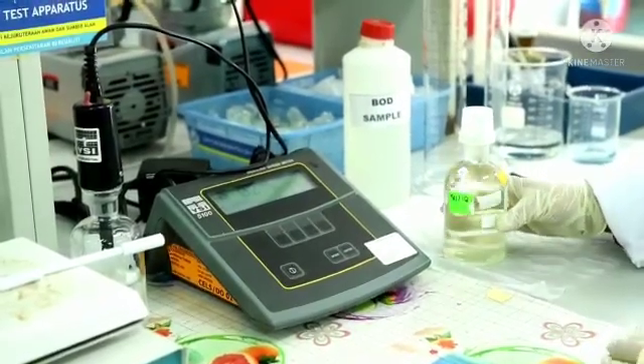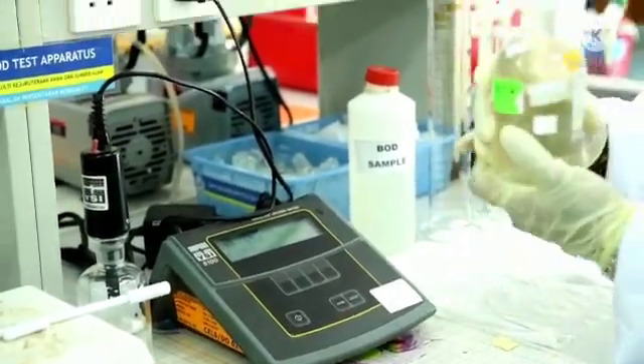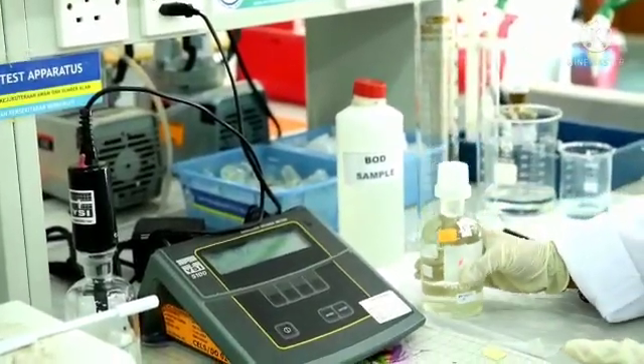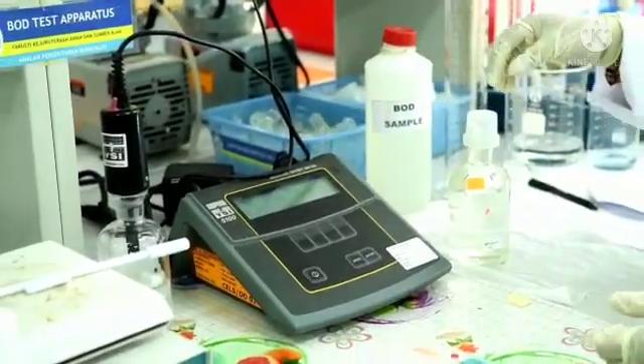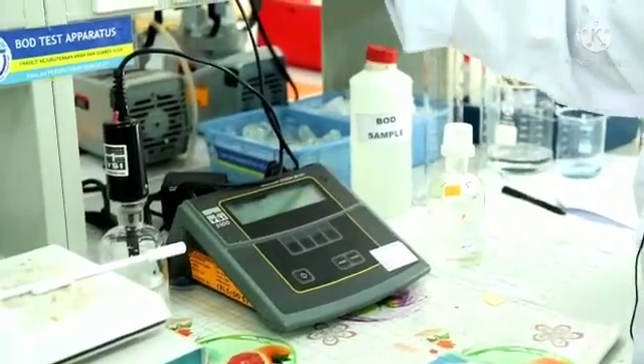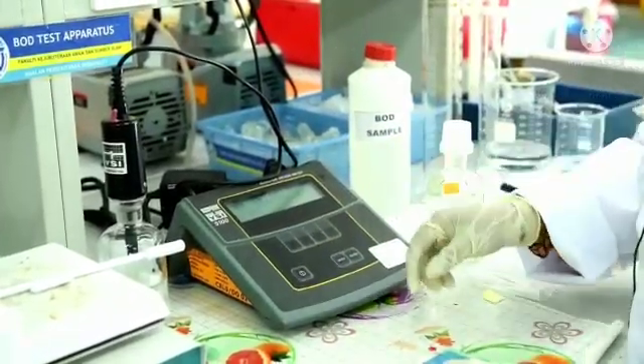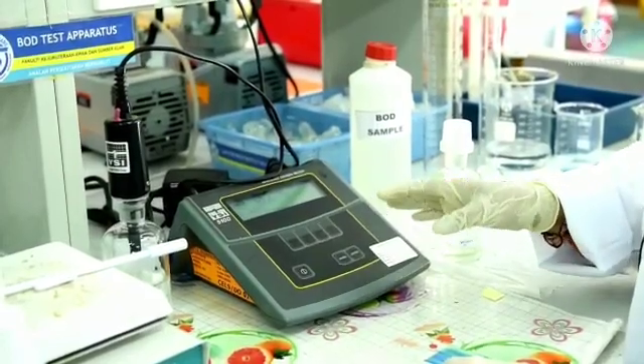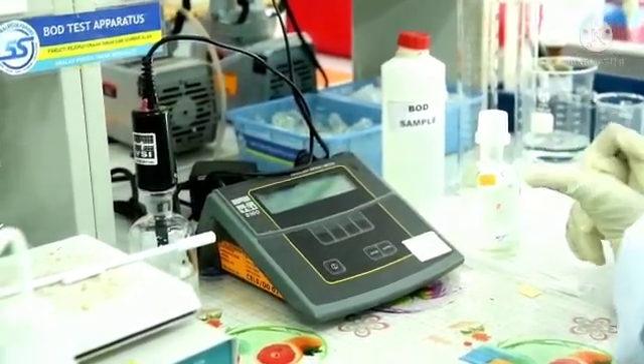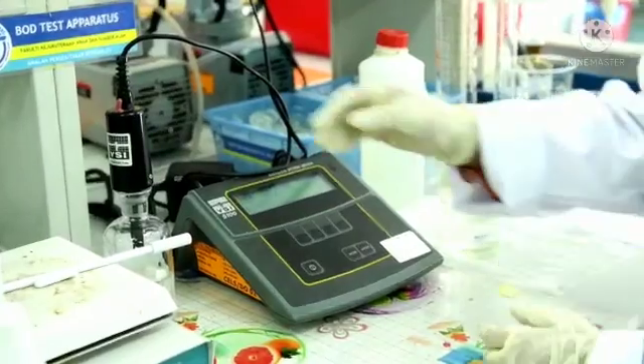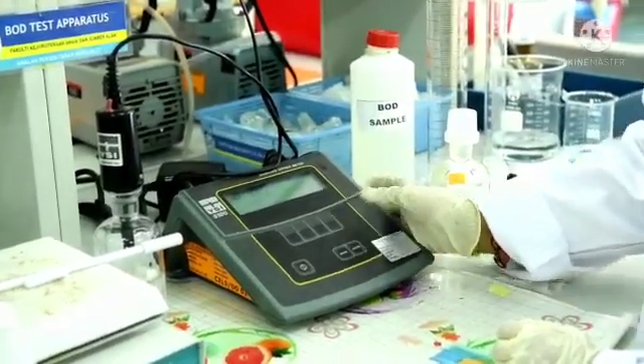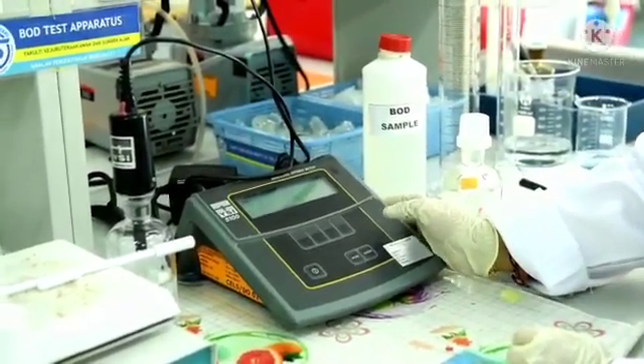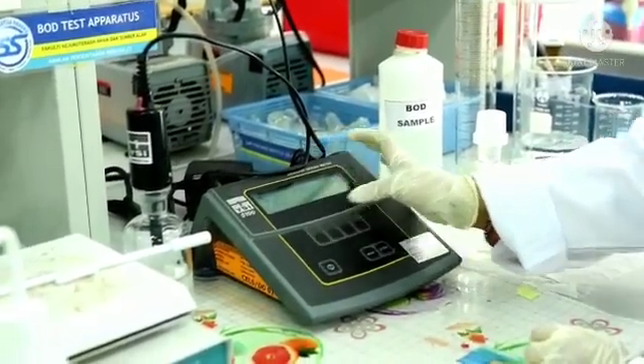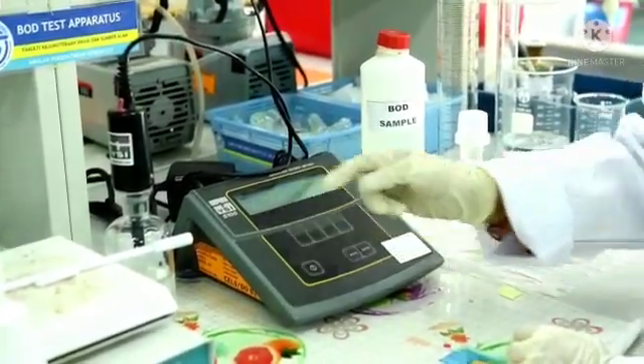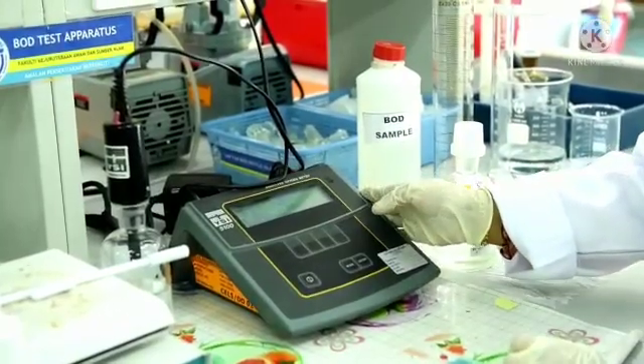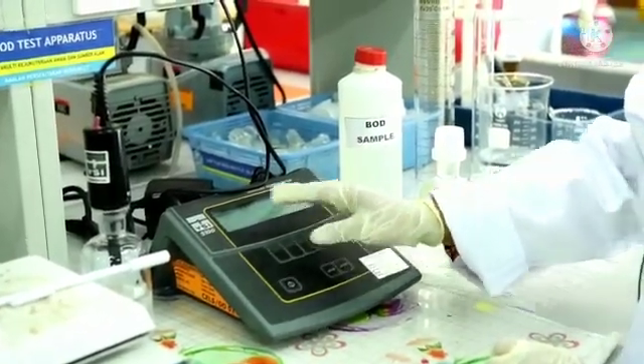After 5 days, we take back the sample from the incubator and read it using the dissolved oxygen meter. Same as before, switch on here and then switch on here. Before you start, you must wait and then press calibrate, auto call, and then mode. So calibrate again, and then press auto call. And then you see here DO calibration save. That means the equipment is stable now. And then press mode to go to the main page.